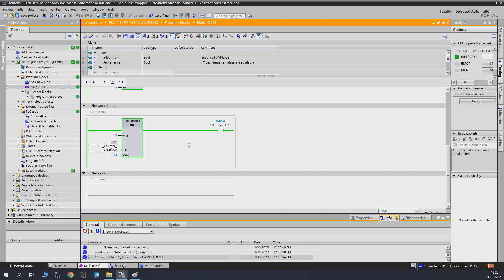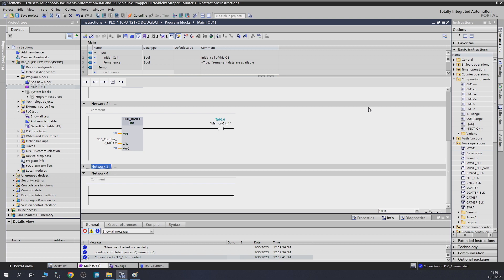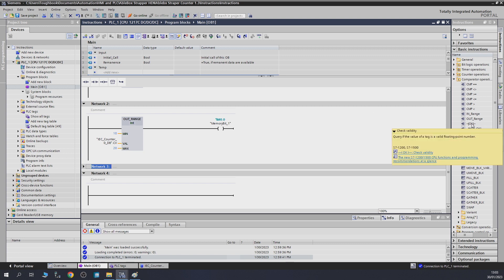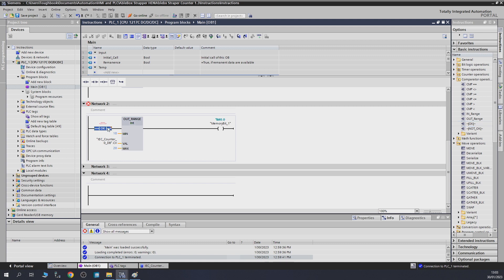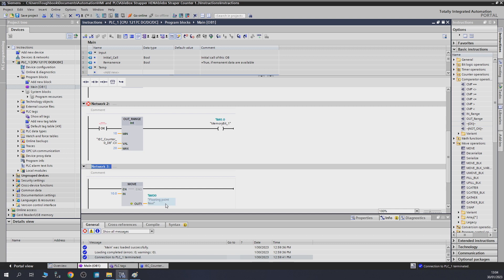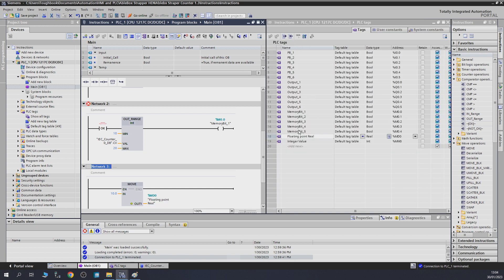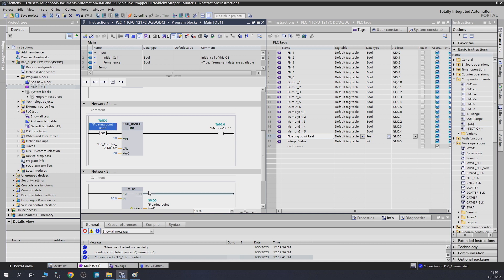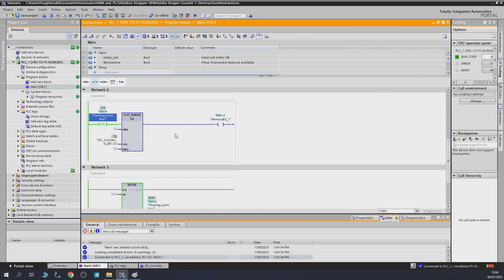Next let's check out Check Validity. This block queries whether the value of a tag is a valid floating-point number — a real value. It only accepts an MD tag, which is a double word. We have a move instruction moving 10.0 into MD0. As long as it sees a valid floating-point value — in our case 10.0 — it lets the signal through. As you can see, the floating point is valid and the signal passes through.